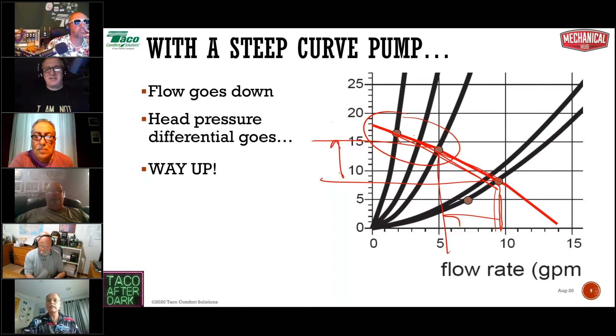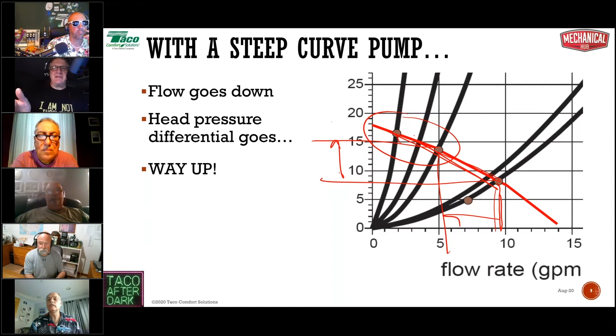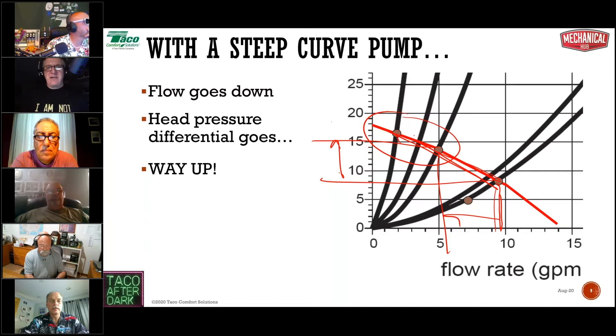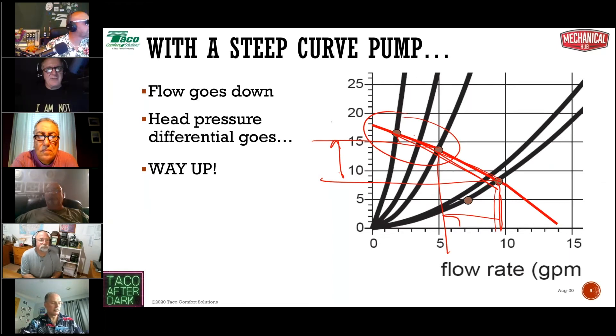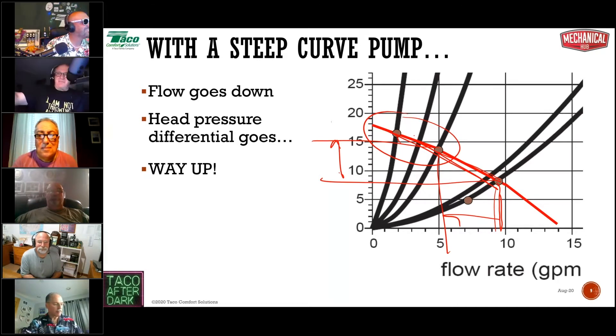So what do people do to deal with this? For some reason it has become the industry standard to install a pressure differential bypass valve on zone valve jobs. But a pressure differential bypass valve is simply a band-aid for a self-inflicted wound — the price you pay for using the wrong pump. What does a pressure differential bypass valve do? In its simplest form, it turns a steep-curve pump into a flat-curve pump. So if all it does is turn a steep-curve pump into a flat-curve pump, why wouldn't we just use a flat-curve pump in the first place?